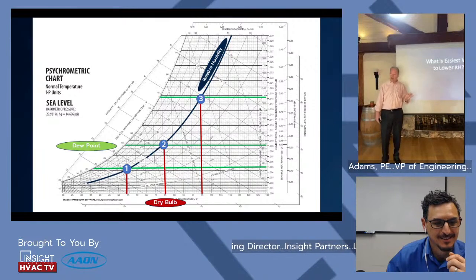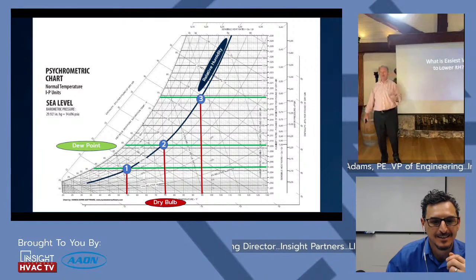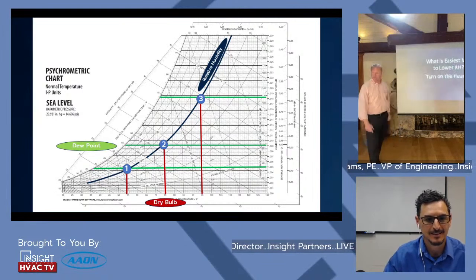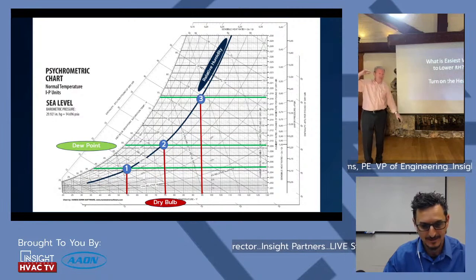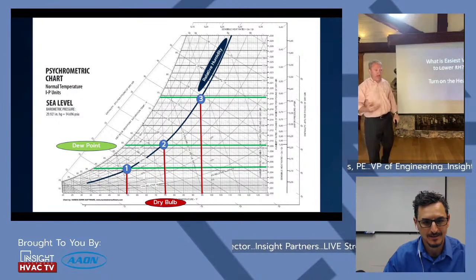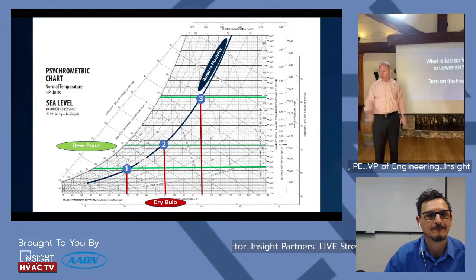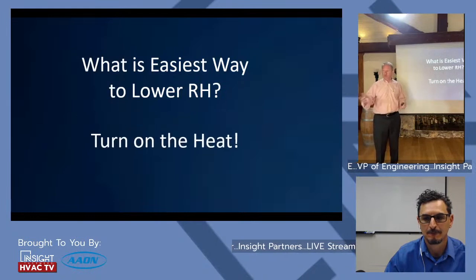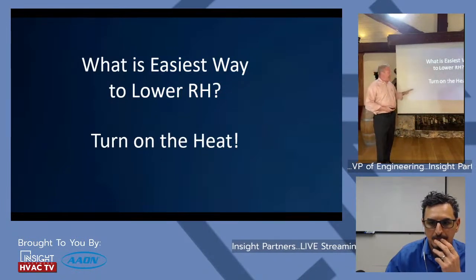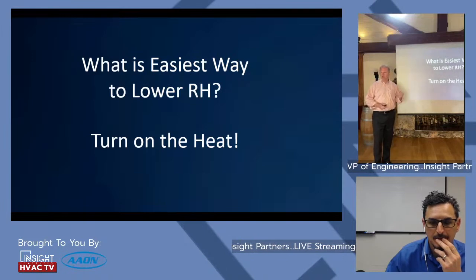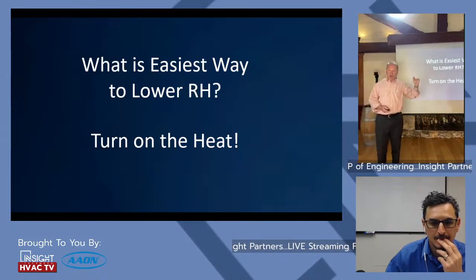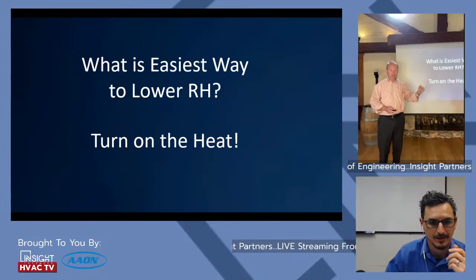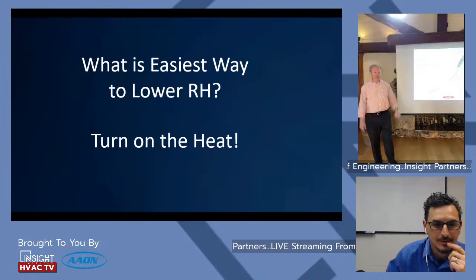When anyone calls and says 'the relative humidity is too high,' my first question is: what's the fastest way to lower RH? Turn on the heat. Warm it up and relative humidity goes down — about 2.1% for every one degree of temperature rise. Temperature is easy to control; heat is easy here in Florida. But it's not easy to get moisture to drop out of suspension — that's where all your energy goes.